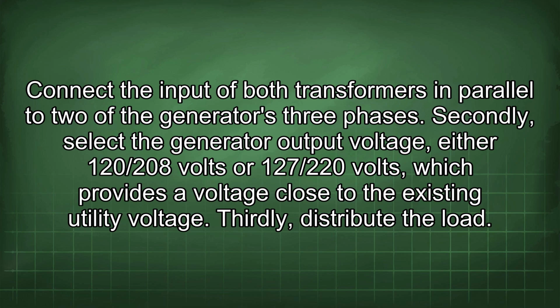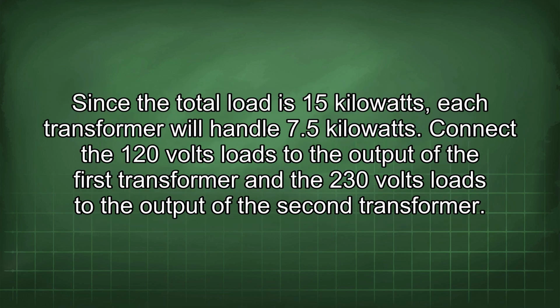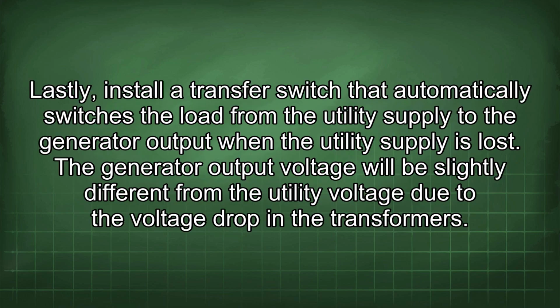Thirdly, distribute the load. Since the total load is 15 kilowatts, each transformer will handle 7.5 kilowatts. Connect the 120 volts loads to the output of the first transformer and the 230 volts loads to the output of the second transformer. Lastly, install a transfer switch that automatically switches the load from the utility supply to the generator output when the utility supply is lost.